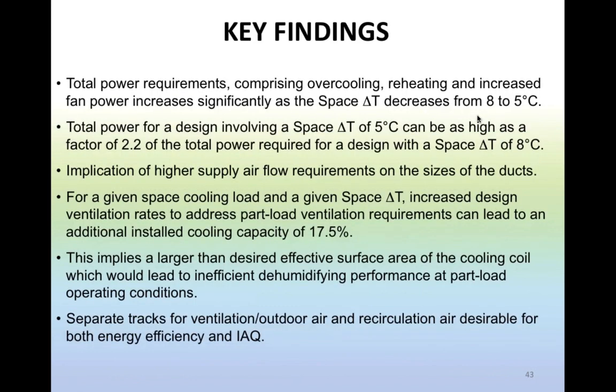So what were the key findings from this particular study? The total power requirements, which comprise overcooling, reheating, and increased fan power, increased quite significantly as the space delta T decreases from 8 to 5 degrees Celsius. So the key point here is, let's try to have space delta T that is larger rather than smaller. The total power for a design involving a space delta T of 5 degrees Celsius can be as high as a factor of 2.2 of the total power requirement for a space delta T of 8 degrees Celsius. And of course, there is the implication of higher supply airflow requirements on the duct size and the associated additional fan power requirements, and the problems that go with it.